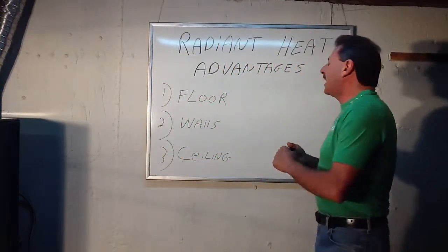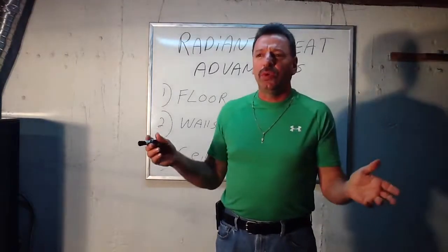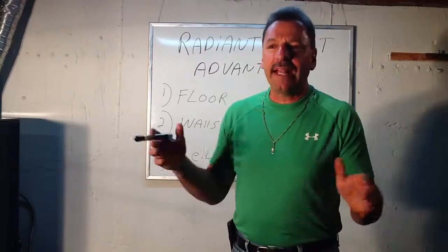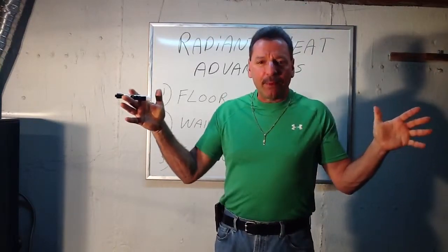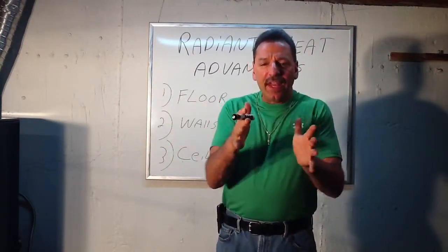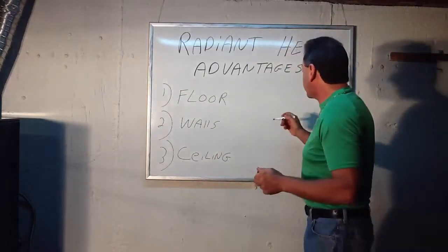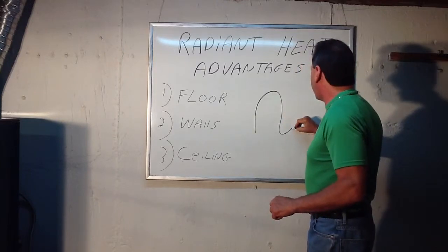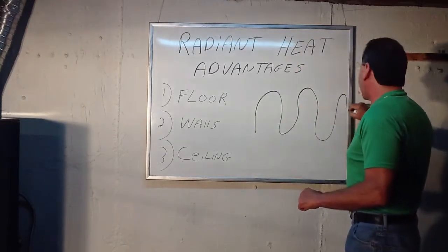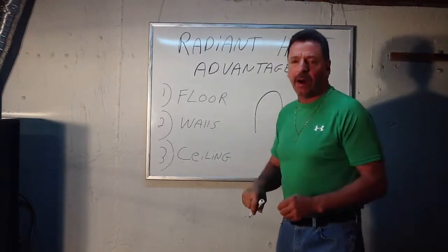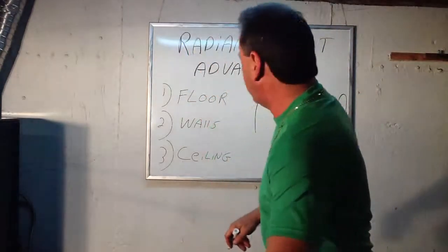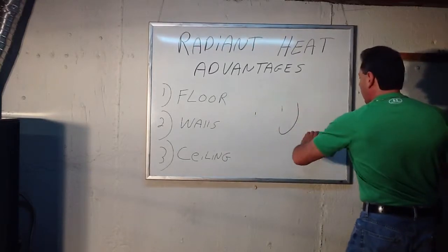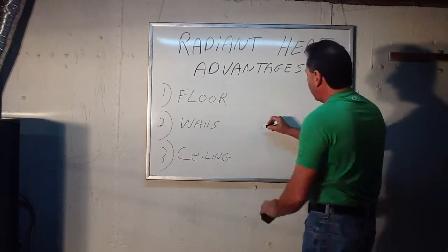And you can't really get a lot more BTUs by putting a larger radiant tubing under the floor, but you can get more BTUs by compressing the inches apart. Normally they'll space radiant heat like this at about 8 inches apart, back and forth, something like that. Of course that's not 8 inches apart, but to get more BTUs out of it, you would simply keep the loops tighter.